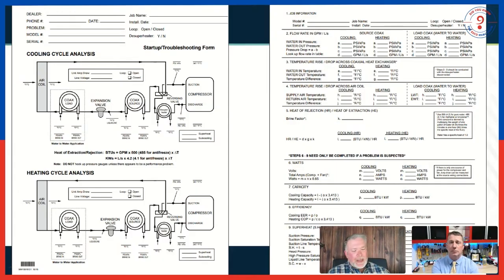If I know what antifreeze is in the system, what my water flow is through the system, and what my water delta T is, I can tell how many BTUs I'm either extracting or rejecting back to the ground. That's kind of my starting point.